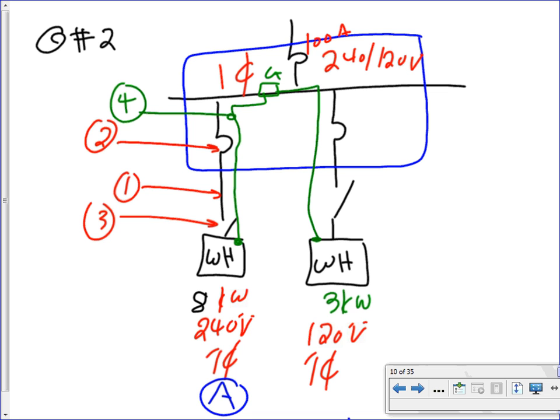So for the water heater, we're doing the same thing. We need a disconnect, we need a feeder, we need an overcurrent protection device, and an equipment ground conductor. What happened to the controller current for the water heater? It's provided by the manufacturer. Don't worry about the controller, unlike motors. That's your question number 2, or B in your list. So we're going to go ahead and do water heater A, which is 8 kW, 240 single phase. We need to do the calculation for the disconnect, the branch circuit, the overcurrent protection device, as well as the equipment ground conductor.